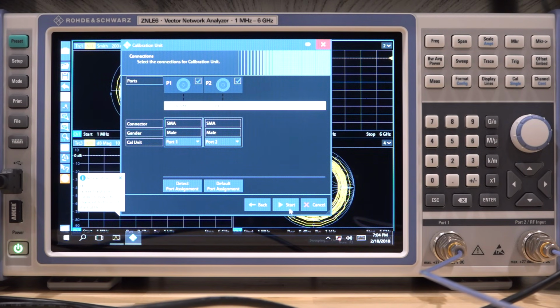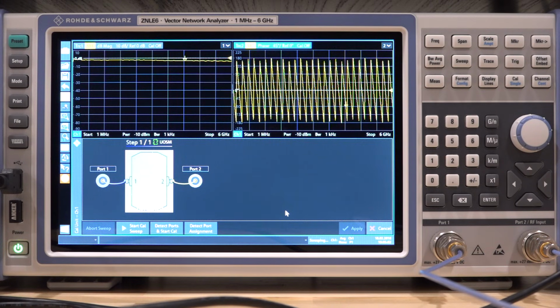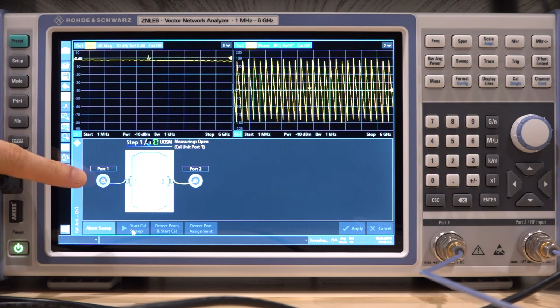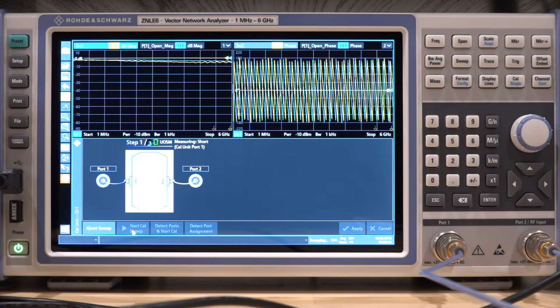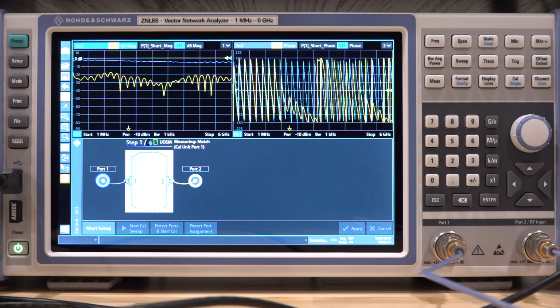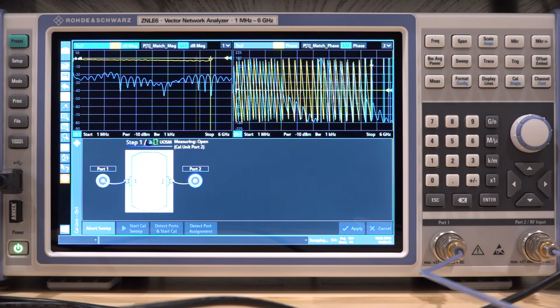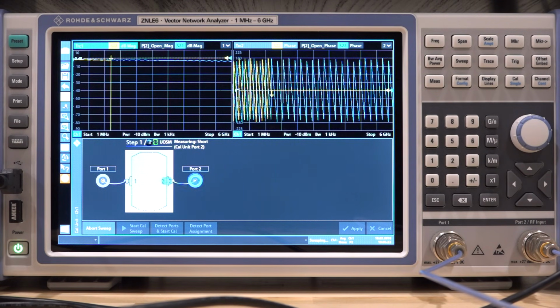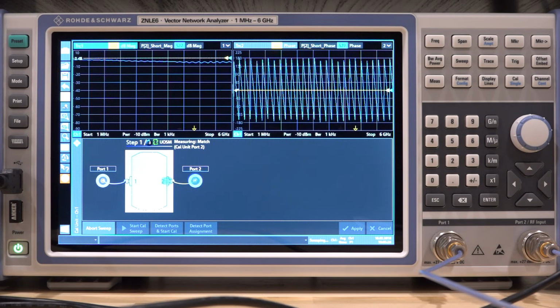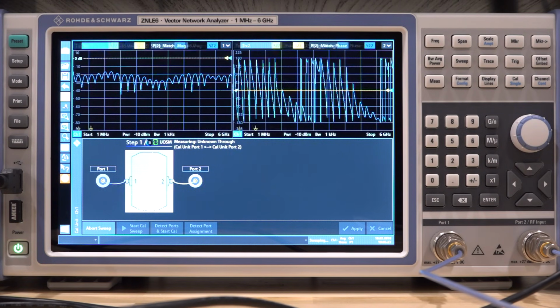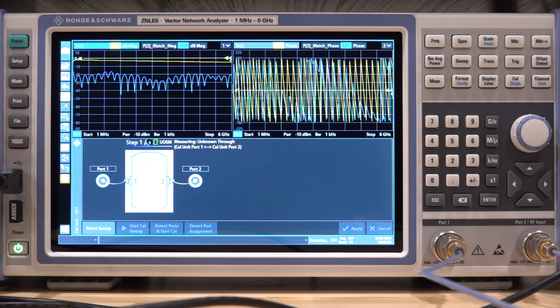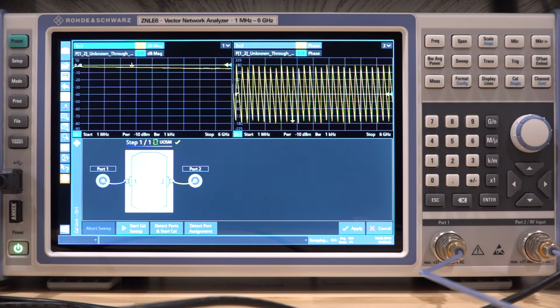Now we go start, and it's going to do a calibration. You can see how that looks like. There it is. You can see exactly what it's doing. It's going to do an incident power. Let me do a full cal sweep there. There you go. So now it's going to do an incident power on the left. It does the calibration on that port, and it measures all the different combinations in order to have the response of it. So we're going to wait for it to go through. There you go. Now it's doing port 2. And once that is done, it should be all finished, and it's going to give us a fully calibrated instrument back. And again, remember I set the IF bandwidth to a much smaller value, so it takes longer obviously to go through it, and we're happy with this, so we're going to apply that.